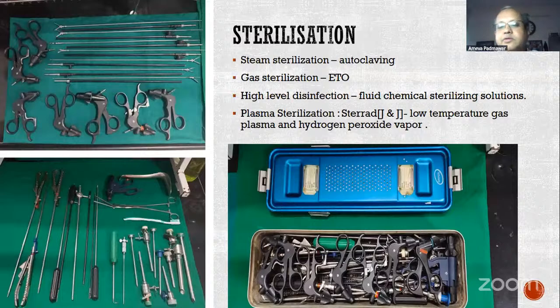Okay, then comes the main step, which I am going to talk about now, which is sterilization. Sterilization of laparoscopy or hysteroscopy instruments is done by 3 or 4 methodologies. One is steam sterilization, known as autoclaving. You have gas sterilization, which uses ethylene oxide gas. Then you have high level disinfection, which uses fluid chemical sterilization. Also not very strongly recommended, but sometimes, especially for optics and electrosurgical handpieces, it is a good way of sterilizing them. But you have to know your chemicals properly so that you can use them appropriately. And last but not the least is plasma sterilization. Plasma sterilization is a boon.